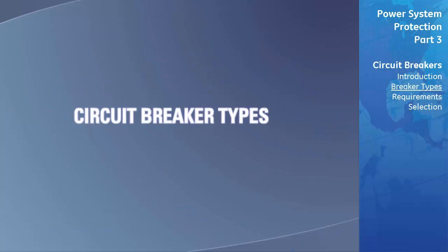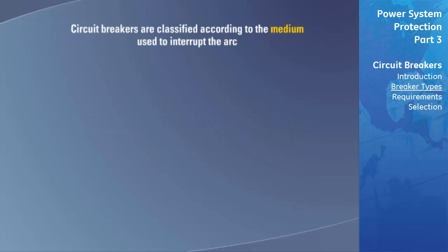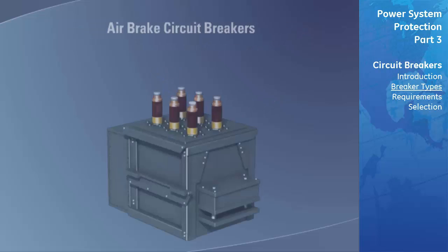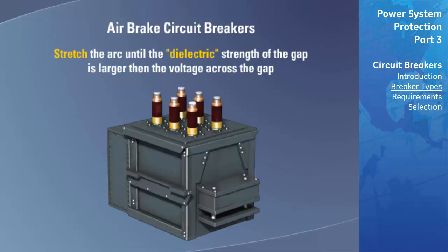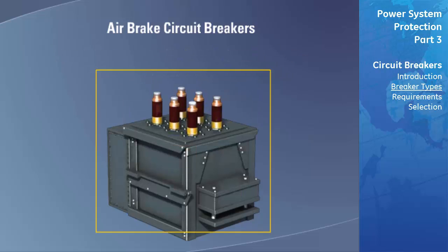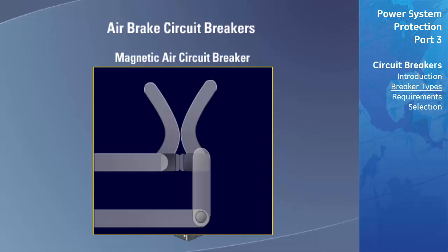Circuit breakers are classified according to the medium used to interrupt the arc. The mediums are air, oil, sulfur hexafluoride (SF6), and vacuum. Air brake circuit breakers extinguish the arc by stretching it until the dielectric strength of the gap is larger than the voltage across the gap. There are various methods employed by different types of air brake circuit breakers to increase their effectiveness.